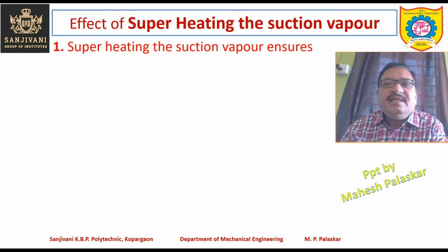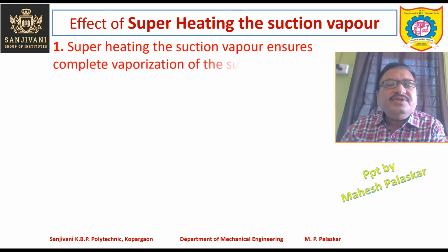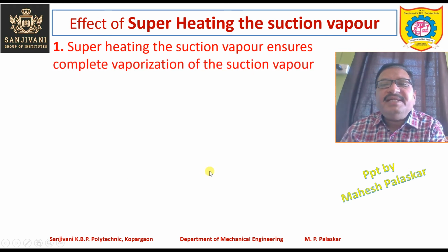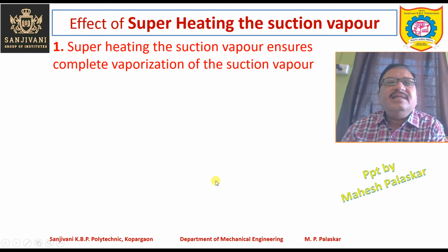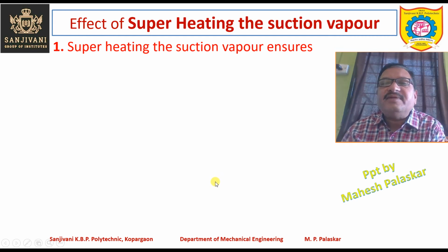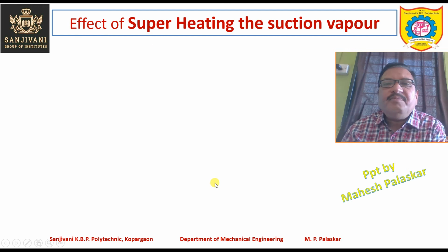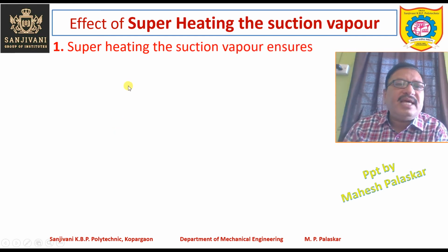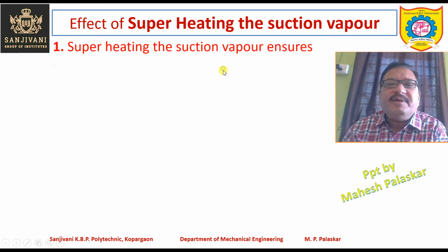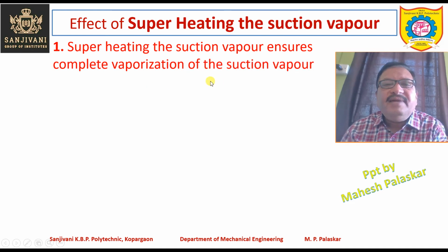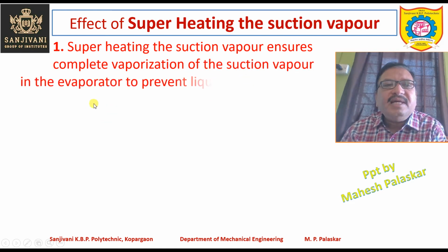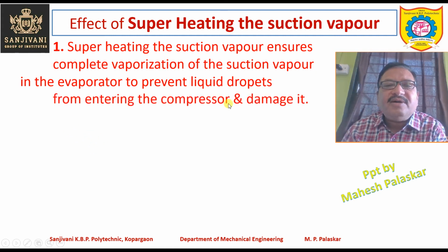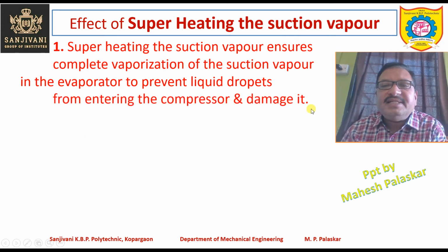So superheating the suction vapor ensures complete vaporization of the suction vapor. Let us study the effect of superheating on suction vapor point wise. So what is the effect of superheating on the suction vapor that we have to see? The first point is that superheating the suction vapor ensures complete vaporization of the suction vapor in the evaporator to prevent liquid droplets from entering the compressor and damaging it.